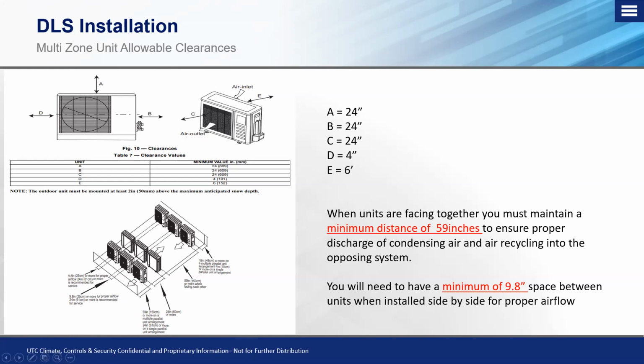Now, when the units are installed side by side, like you see here, we need to make sure that we have a minimum of 10 inches of space between the units for proper airflow. Typically, I'd like to say between 12 and 24 just for service access, but if you do have to keep them close because you have to maintain a tight perimeter, because you're working with a very small space that you have to put these units in, the minimum we have to have is at least 10 inches for proper airflow from the sides of the unit.